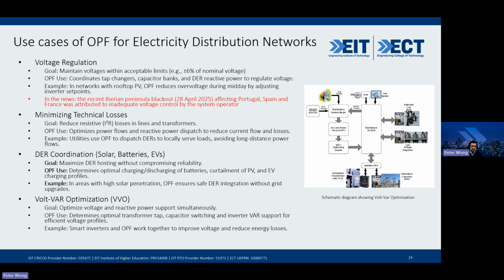Another use case for OPF in distribution networks is to minimize technical losses, similar to what happens on the transmission network. You run it to reduce technical losses, which in many cases means using generation that is close to the load. Instead of generation coming from a far-away central power station, you dispatch the generator closest to the load, reducing the path electricity has to travel, and therefore reducing losses. That's another use case of OPF, running power flow with the objective to minimize technical losses.